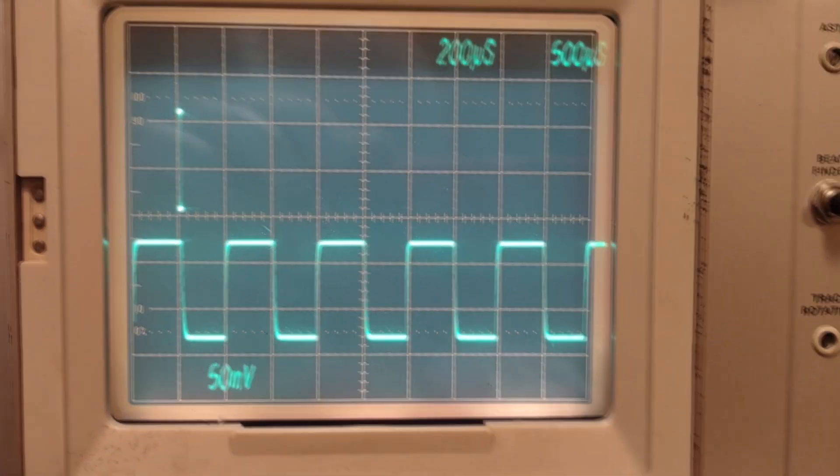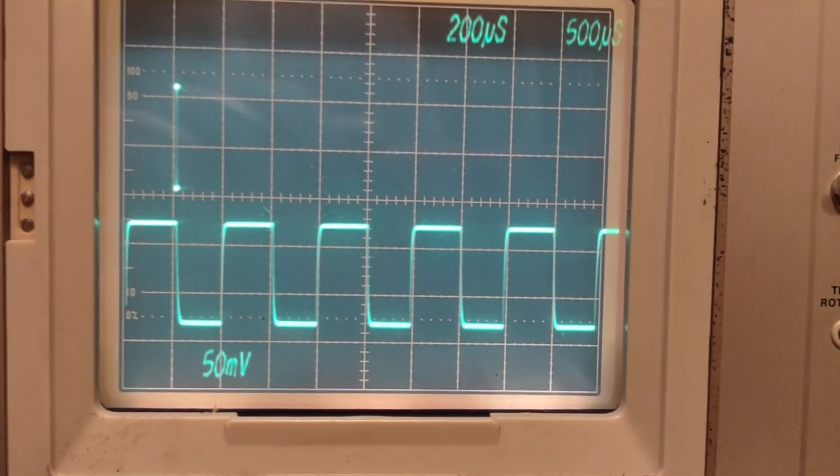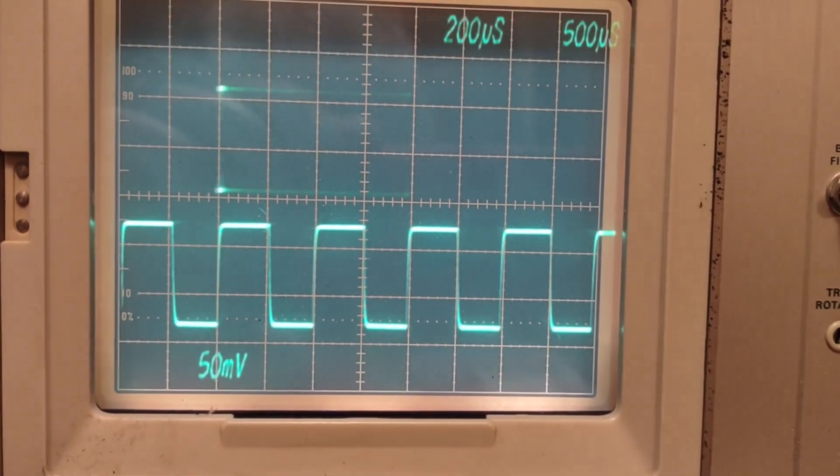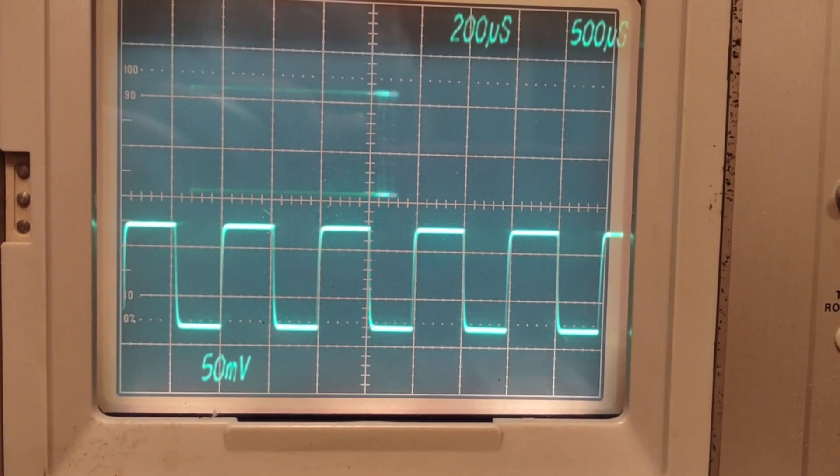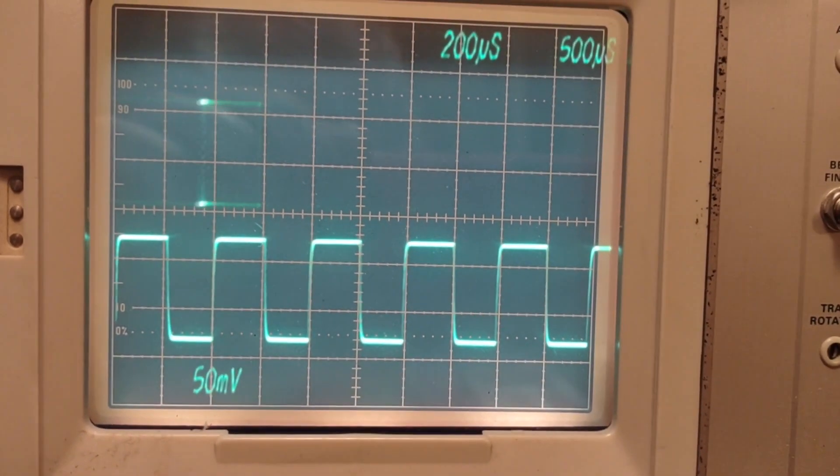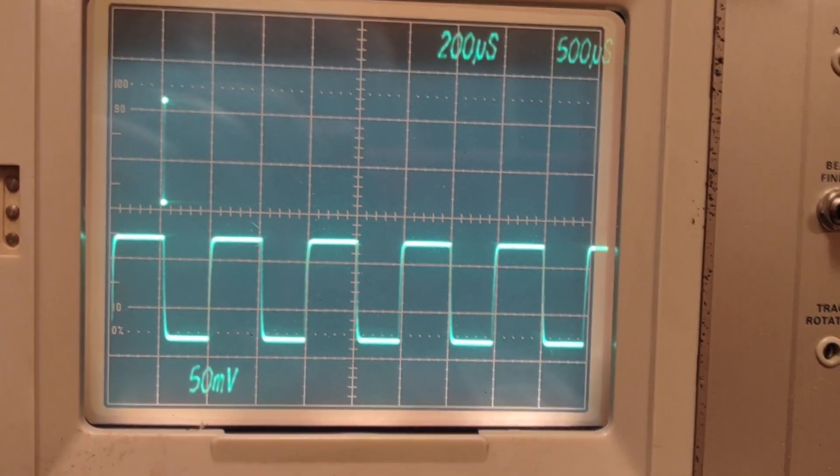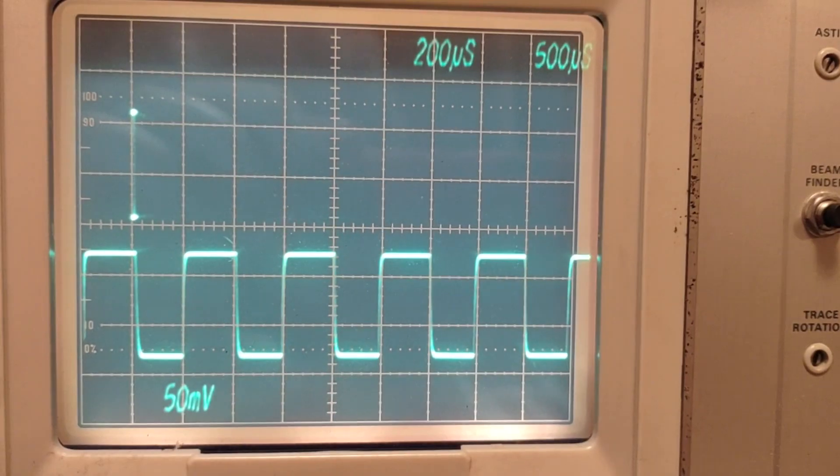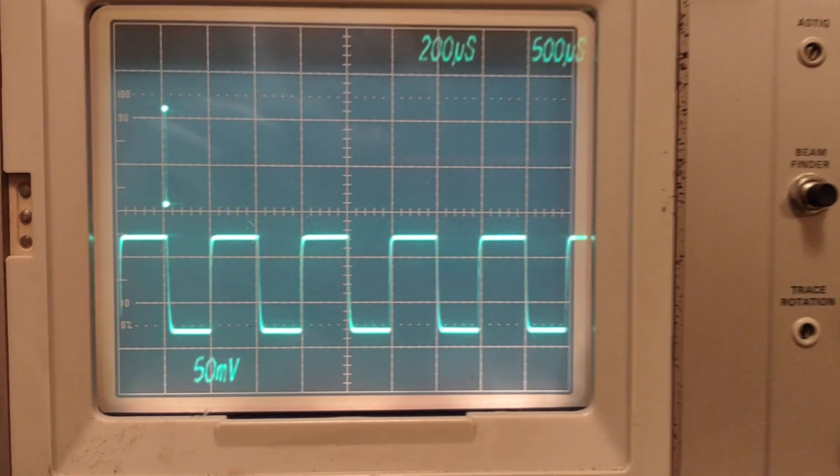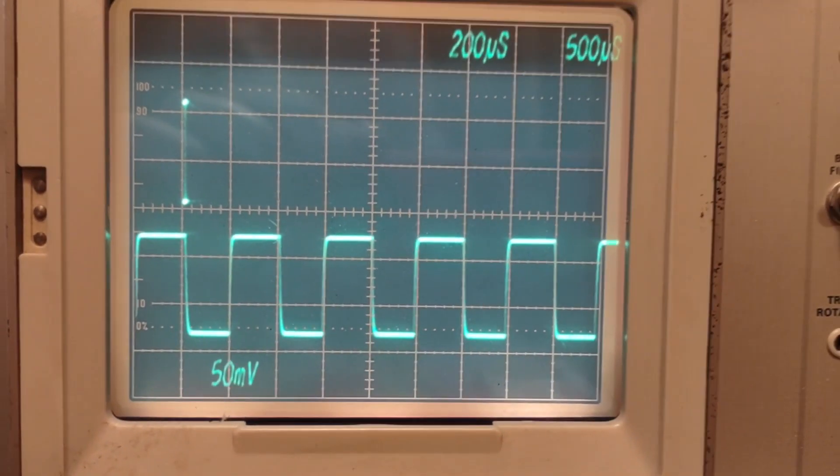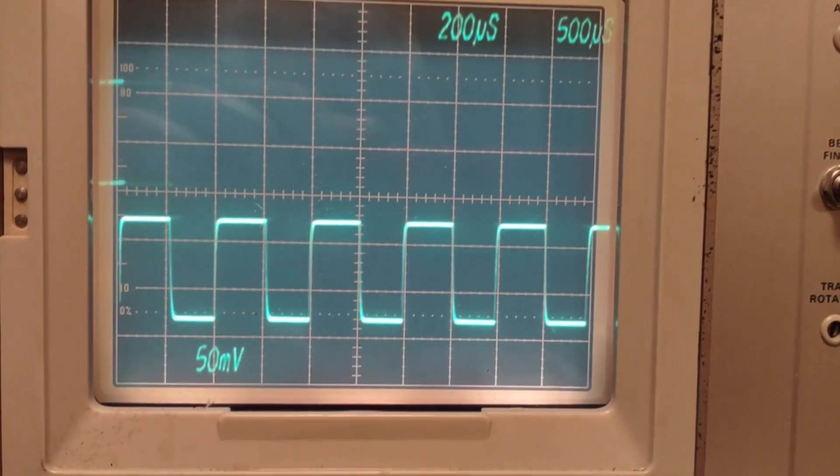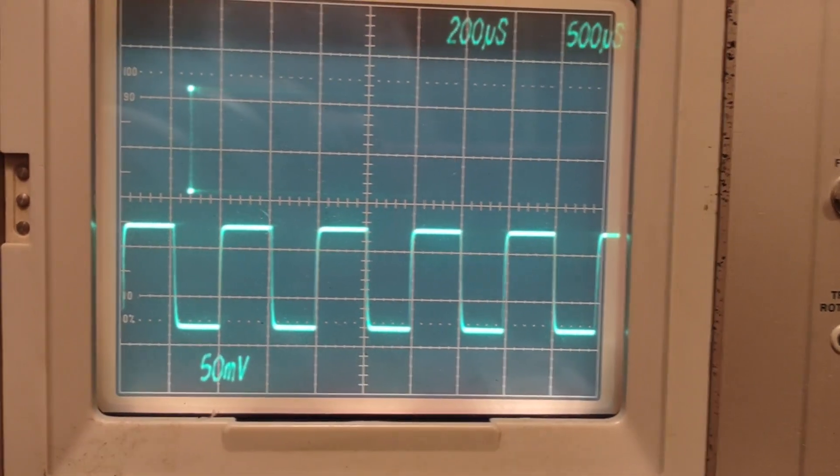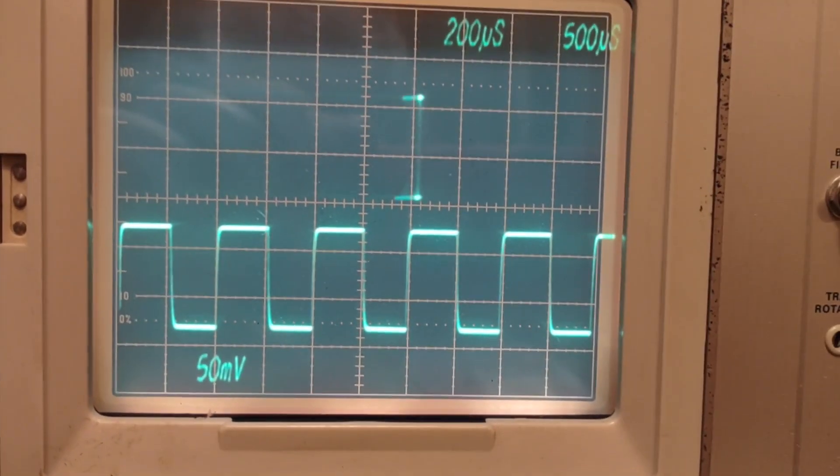This display was produced with two 7B53As in the mainframe, one working and one not. The lower trace is the working unit. The upper trace shows only the top and bottom of the square wave. The dots can be moved with the position control, indicating the problem is not in the plug-in's horizontal output circuit.